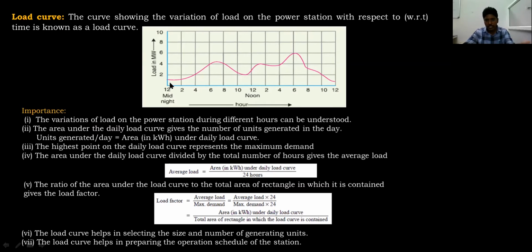So from this one, we can conclude that area under the load curve gives you the total number of units generated in a day. And if you want average demand, meaning average load, the area under the load curve divided by 24 hours gives you the average load. Load factor means average load by maximum demand. Average load we already got from here, and maximum demand we already know. Therefore, we can find average load, maximum demand, number of units generated, and load factor from load curves.